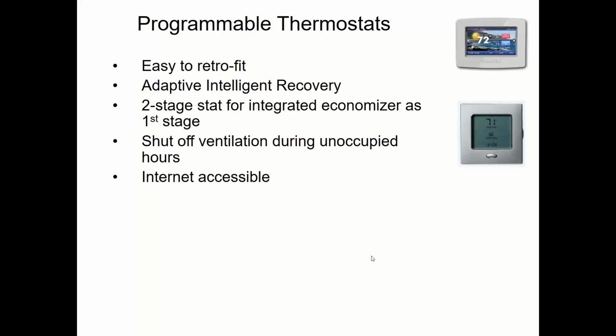Now, technically, most ventilation codes allow you to have up to 2 hours of occupied time that's not ventilated. Typically, that's meant for transient spaces. Like if you don't want to ventilate your hallways, you don't necessarily have to, because people are only there for a couple minutes. It's not really meant for this. People try to shove it down that way. So you should probably continue ventilating your building all the way till the 5 p.m. time or whatever time you establish.